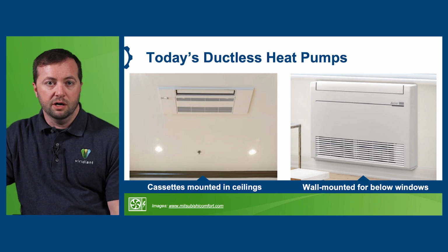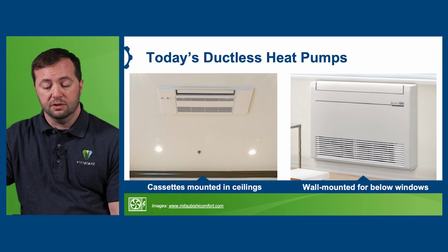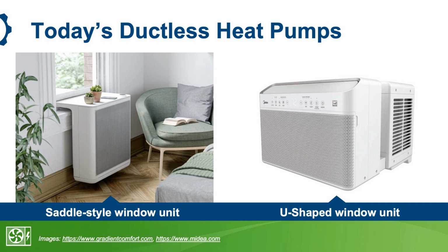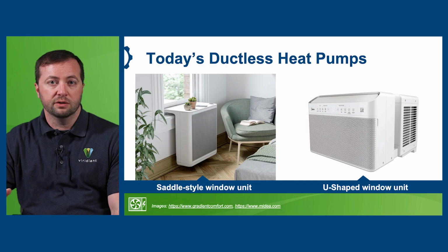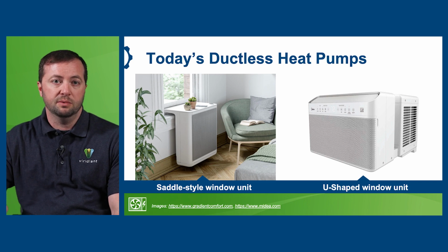All of these air handler options could work off of one main outside unit. There are also some packaged units that are newer to the market and are in fact heat pumps, even though they may not look like it. They're called packaged because the compressor and the air handler are part of a single piece of equipment instead of being split between the inside and the outside like a standard split heat pump.